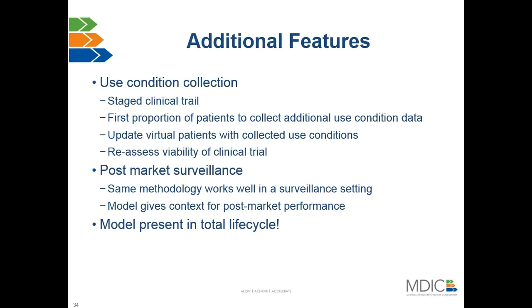Okay, some of the other features of this method, one of the big ones is the collection of use conditions. So one of the things that some really clever people always ask me is they say, well, in your paper on lead fracture, you had to X-ray people with that device. Well, how can you do that before the device is released to the general population? Good question. So what we brought into the method was that the first proportion of the patients in the clinical will actually be implanted with the device, but not only will they be monitored for the response or the outcome of the clinical trial, but they also will be used as the input.